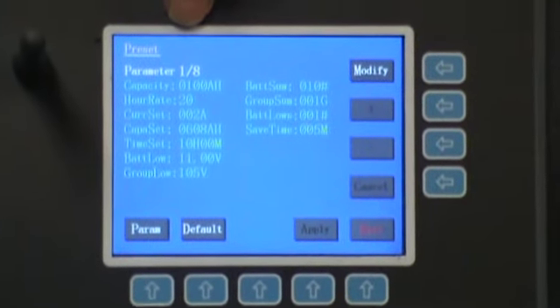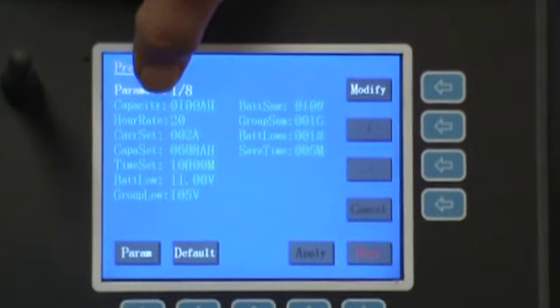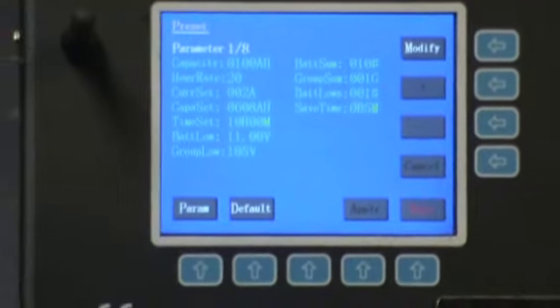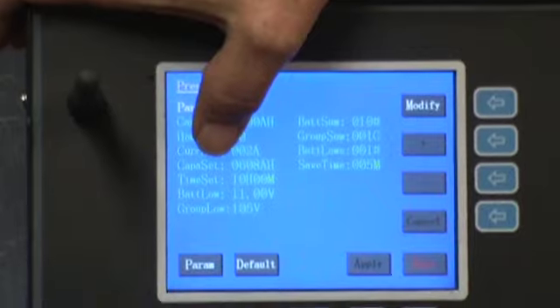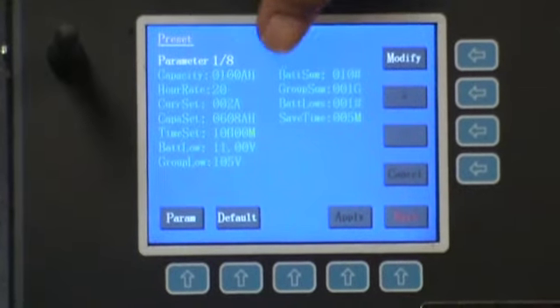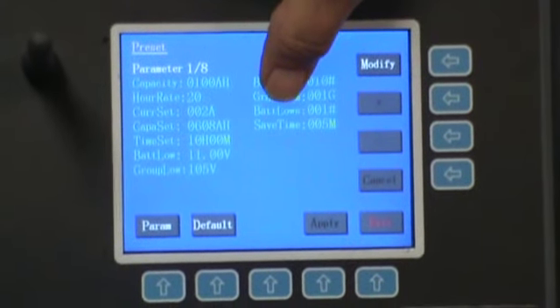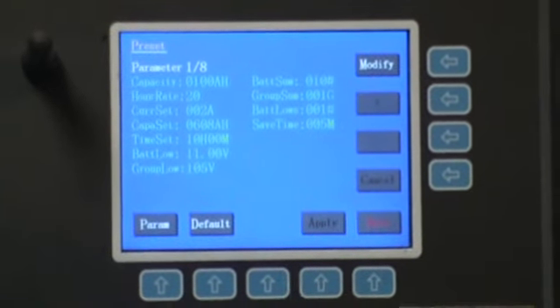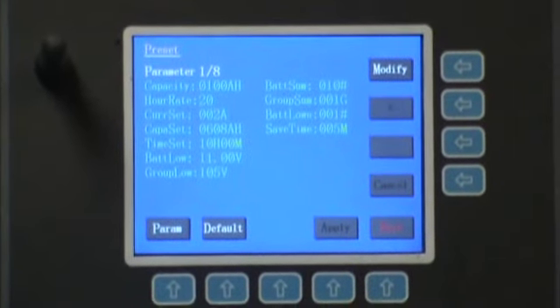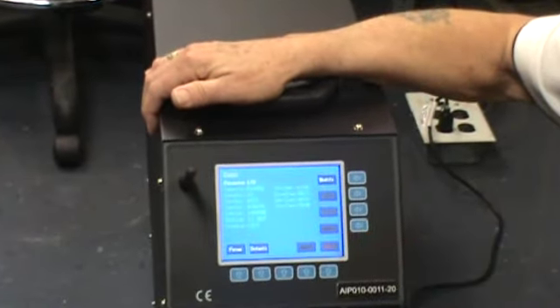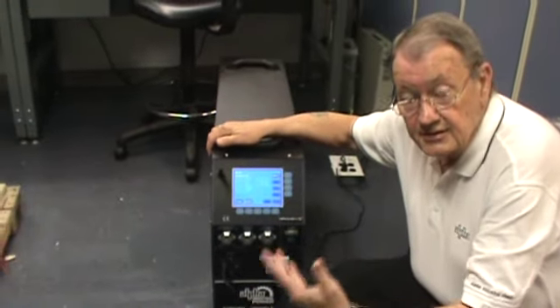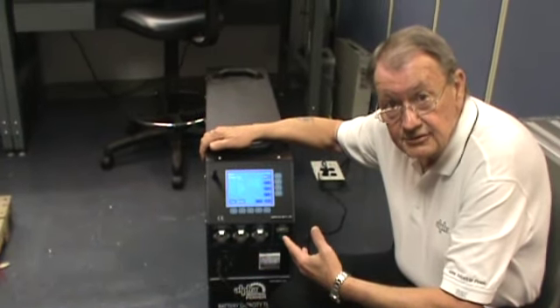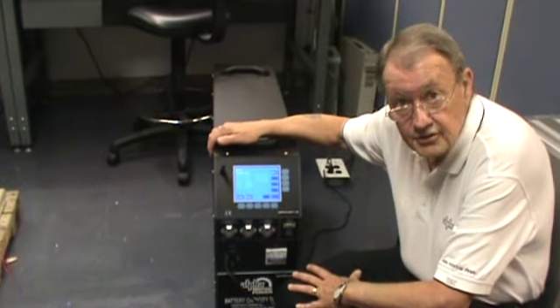The parameters, for example, under the preset: we can set the capacity of the batteries, the hour rate, and the current that we want to run the batteries at. We can set the capacity setting, the time, battery low, group low, battery sum, group sum, battery lows, and how much time we want the unit to go before it actually stores the data. As you're running the test, I've got it set now, for example, to 5 minutes. Every 5 minutes it will capture the data and store it, and later on we can retrieve that data out of the unit.